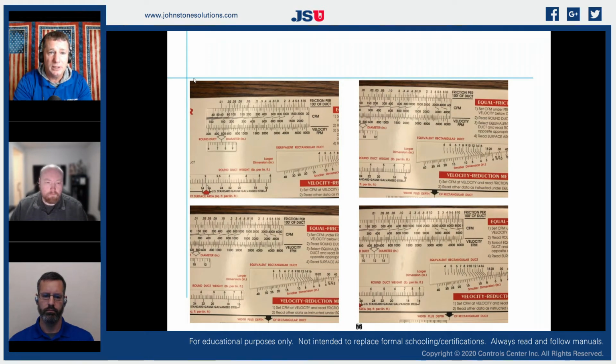If I look at, let's see, 422, that would be this third one down here. If I look at 400, approximately 422 CFM at 0.1, that is going to give me my dimensions that I can run, okay? If I was working with round duct, I'm larger than a 10, so I would have had to use a 12, but we're working with rectangular for this particular installation.